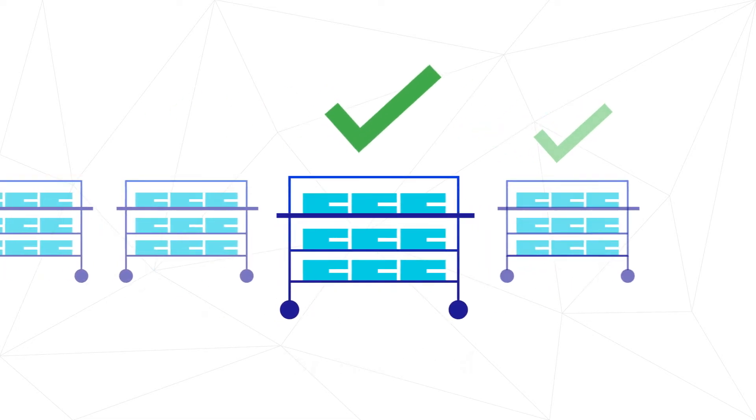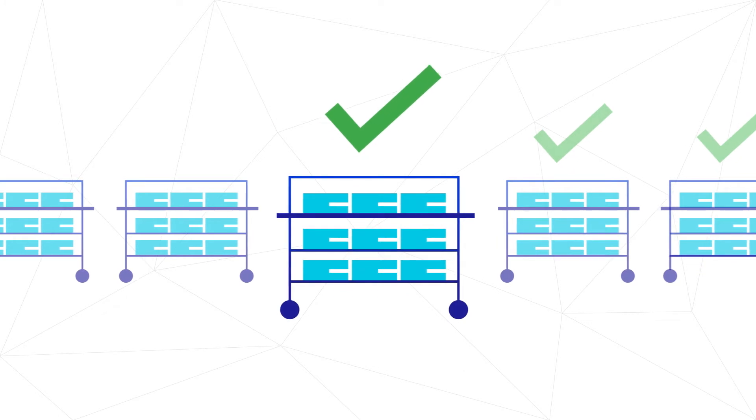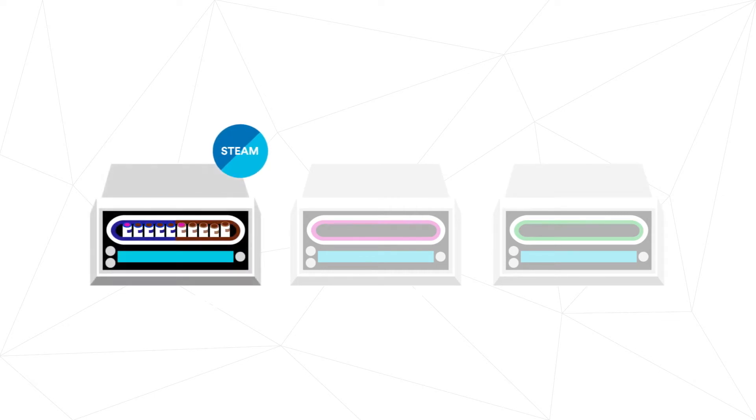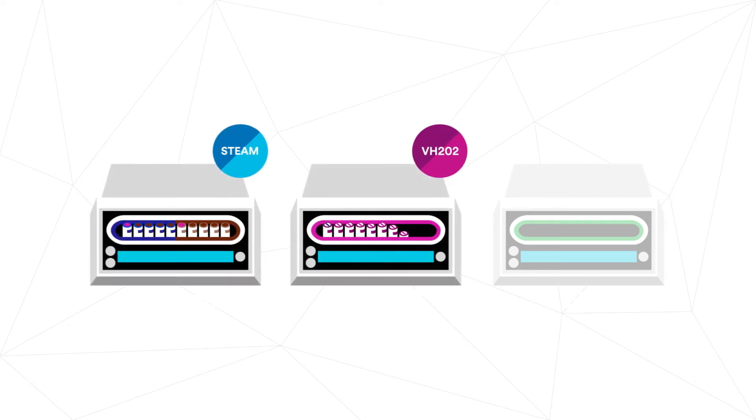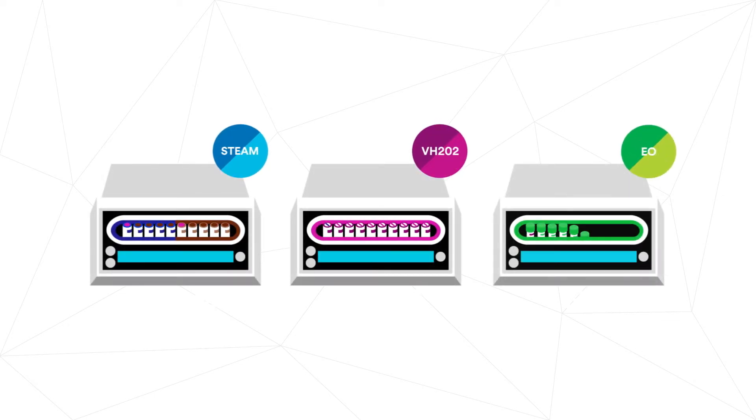Faster results for vaporized hydrogen peroxide sterilization make it practical to do every load monitoring across steam, vaporized hydrogen peroxide, and ethylene oxide sterilization modalities.